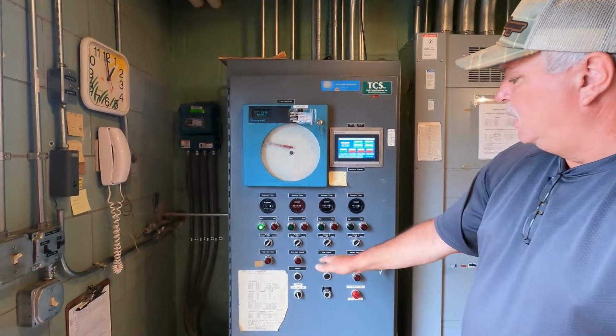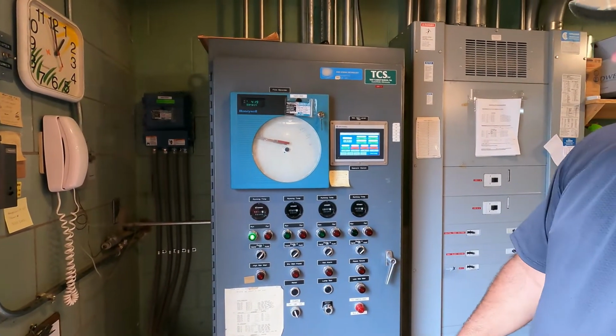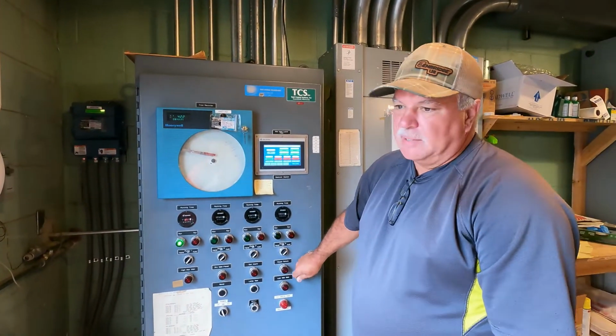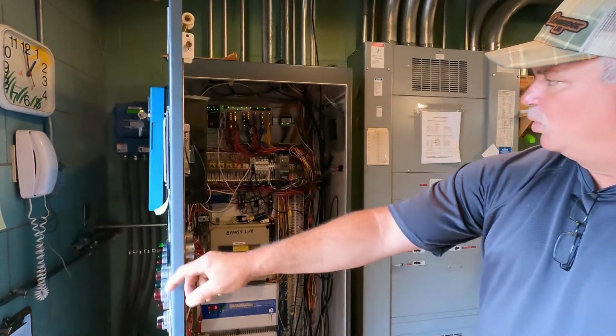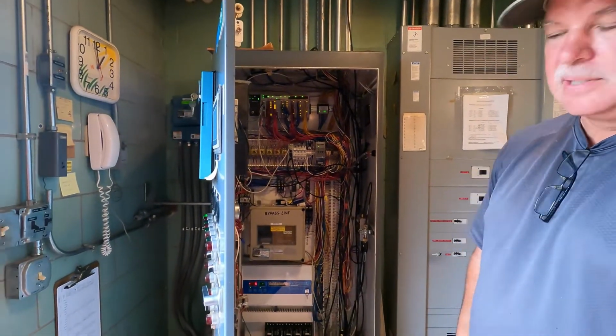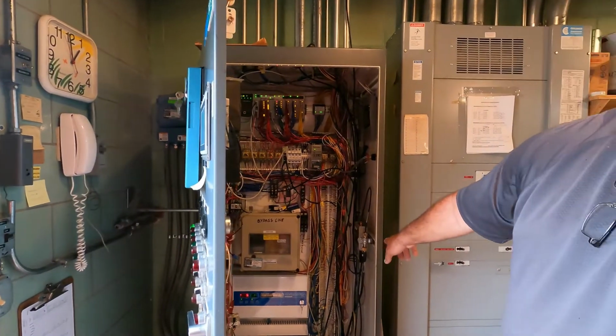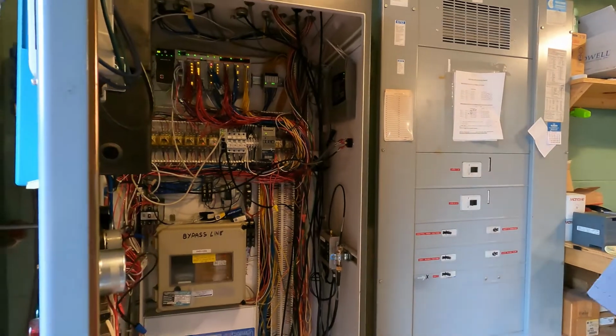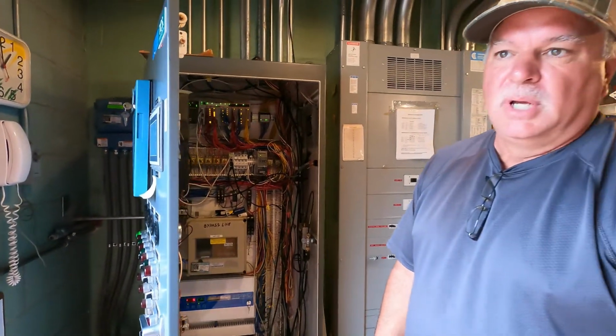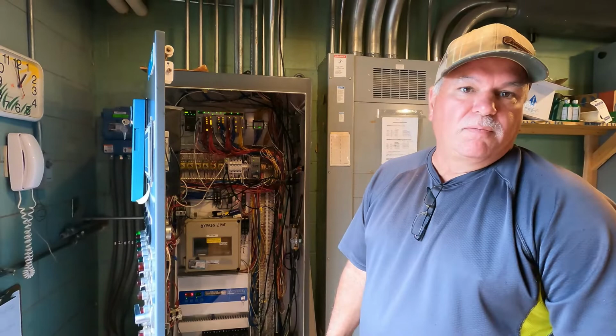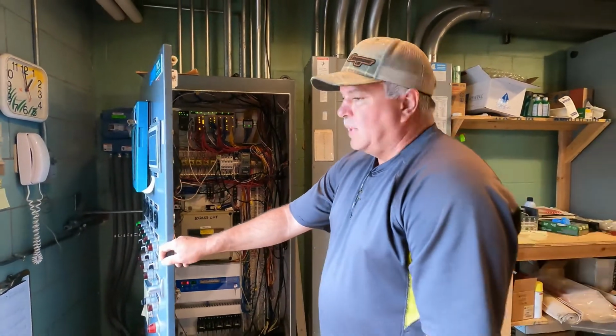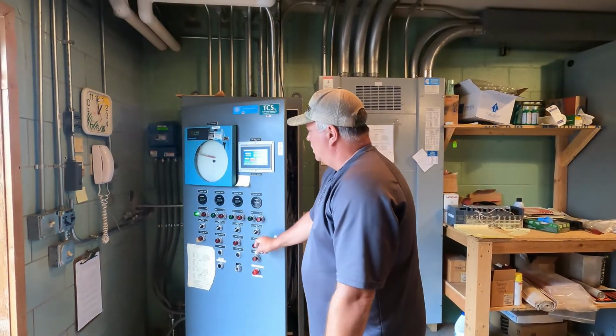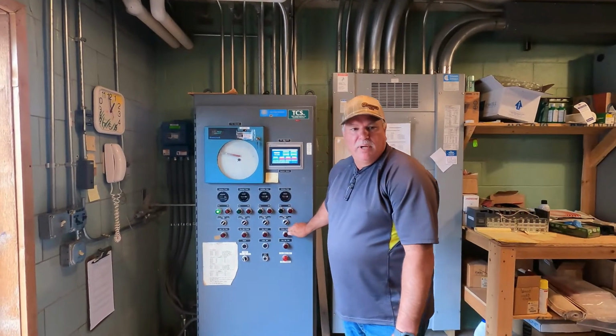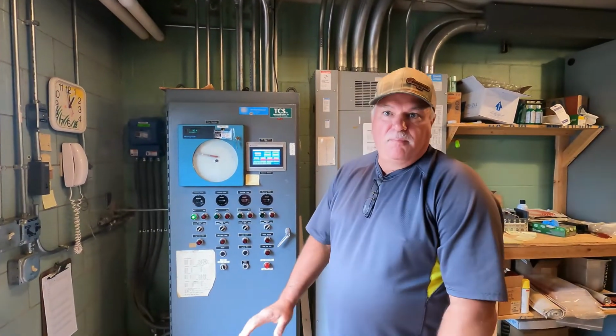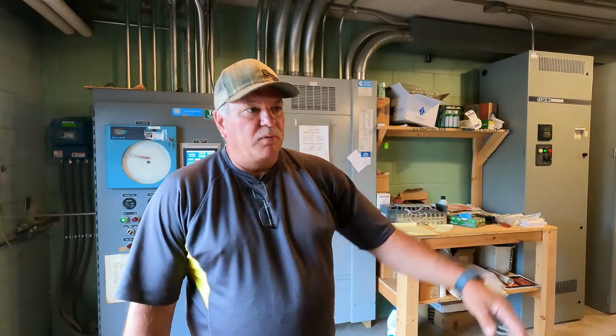Switches for each pump, reset buttons for any alarms that would go on. Inside the panels, the PLC is programmed to run all the transducers and the speeds of the pumps. Radio for alarm systems. We've got high wet well alarms, low wet well alarms, power fail alarms, and pump fail alarms as well. So if the pumps would trip out in any way, we'd be notified at the plant certain hours of the day, and after that we'd be notified at home as well.